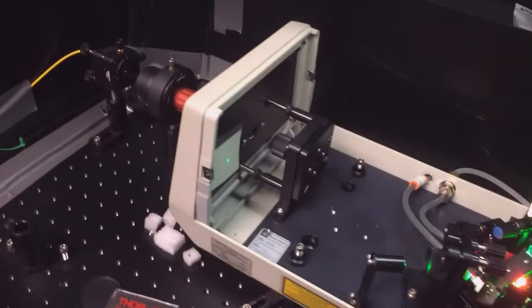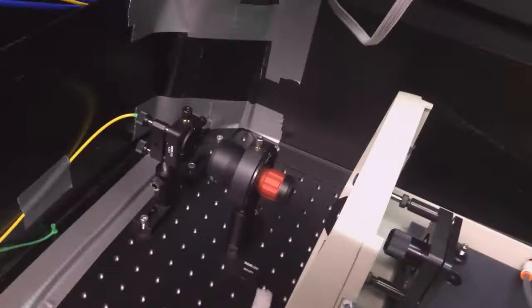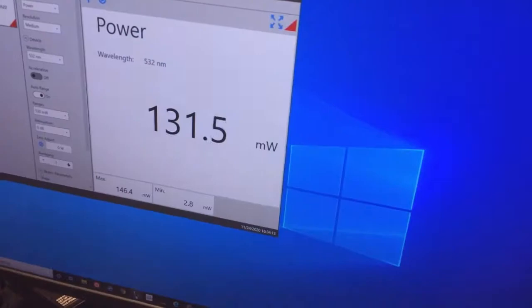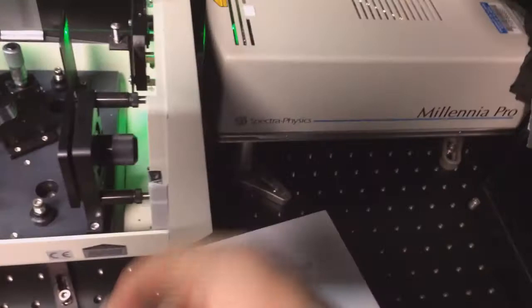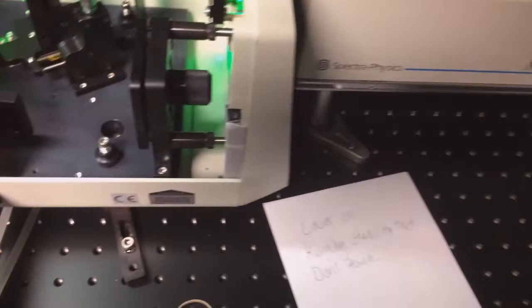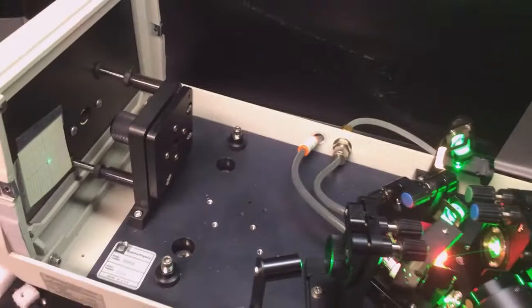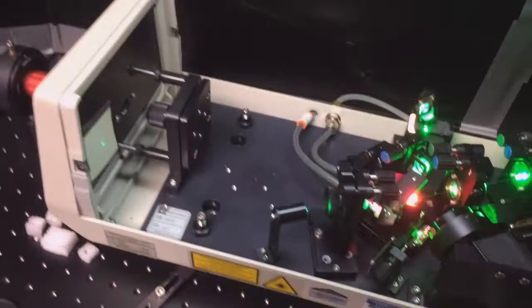Now it can be helpful to set up the power meter after the single mode fiber or directly before the laser if you are doing initial setup. So here we have the power meter on the screen. Now often it is good to adjust the high reflector, the back reflector, to match its mode that is reflecting back to the output coupler which is right there, centered in the camera. The output coupler adjusts the output mode so if you are coupling single mode fiber it will be very sensitive as to the coupling.